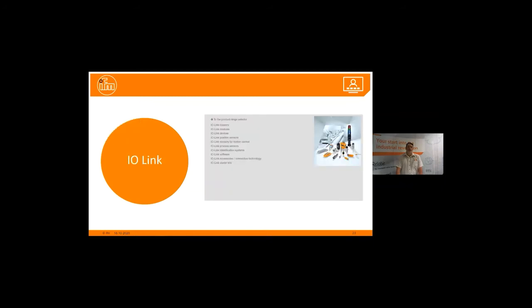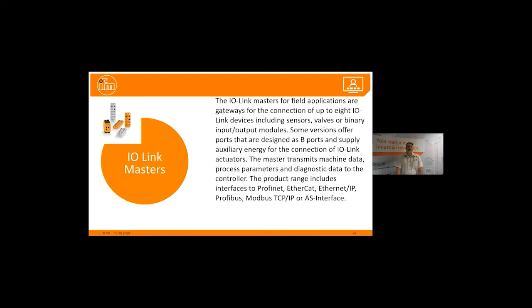Over to IO-Link. Once again, the menu shows a variety of options available under our IO-Link platform. Let's discuss some of them. The IO-Link Master itself: IO-Link Master for field applications or gateways for the connection of up to 8 IO-Link devices, including sensors, valves, or binary input and output modules. Some versions offer ports that are designed as a B port and supply auxiliary energy for the connection of IO-Link actuators. The master transmits machine data, process parameters, and diagnostic data to the controller, your PLC in other words.